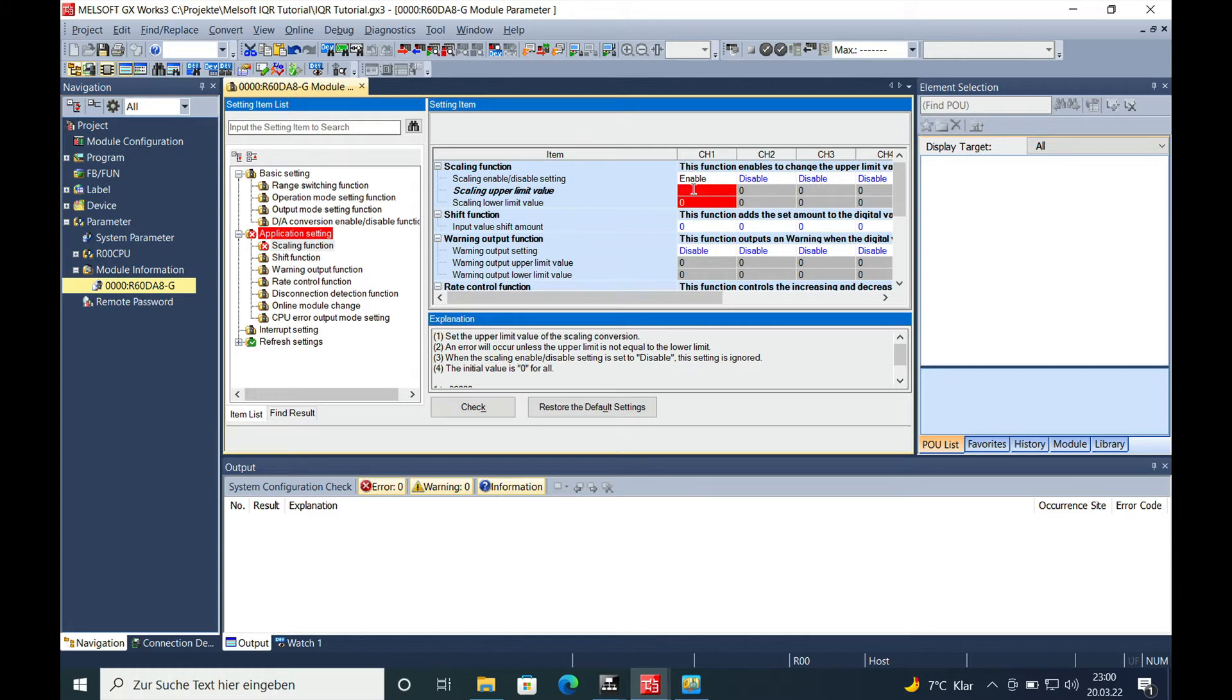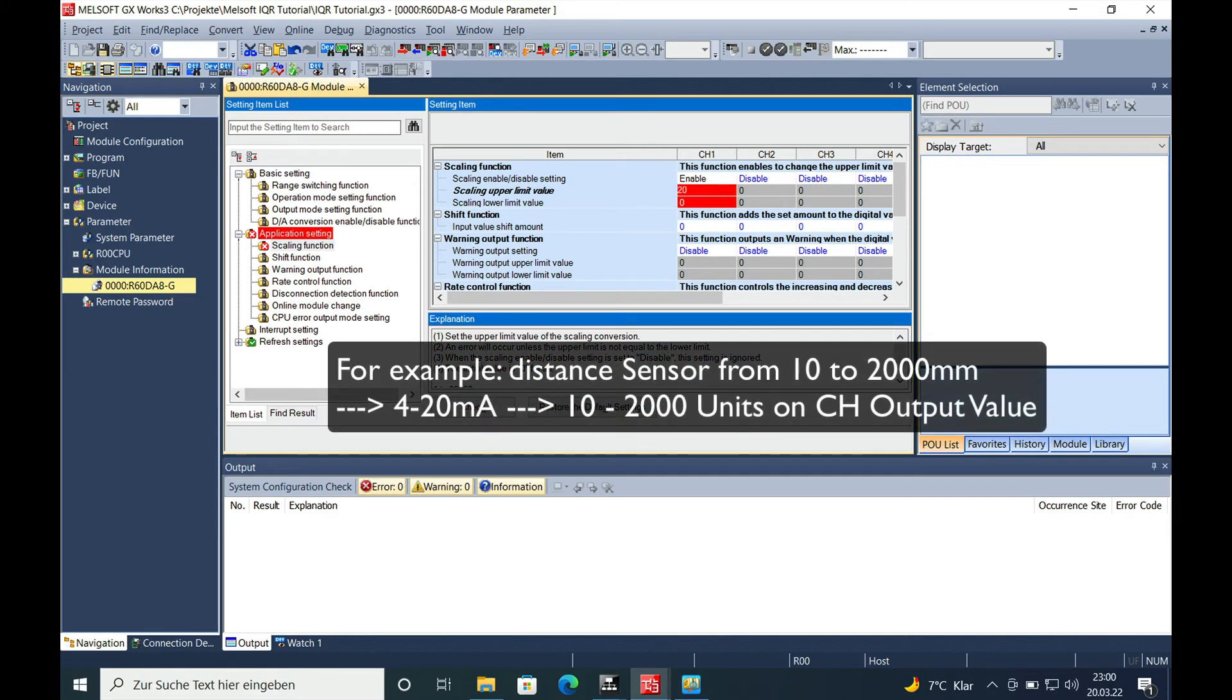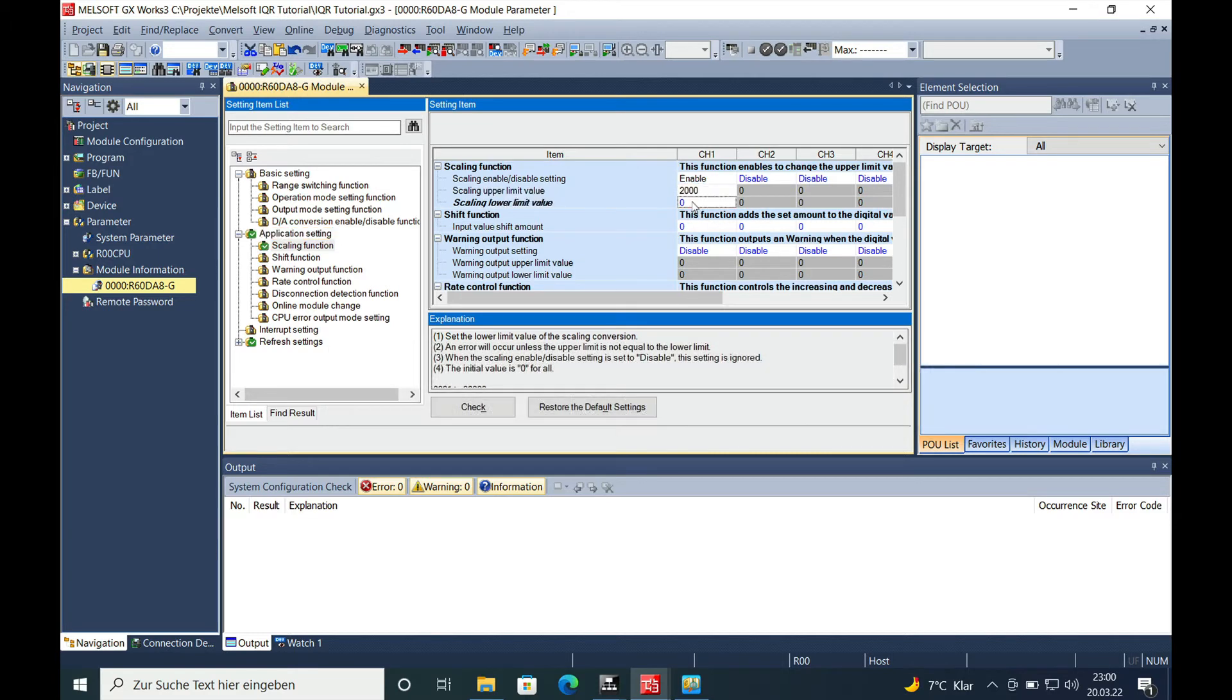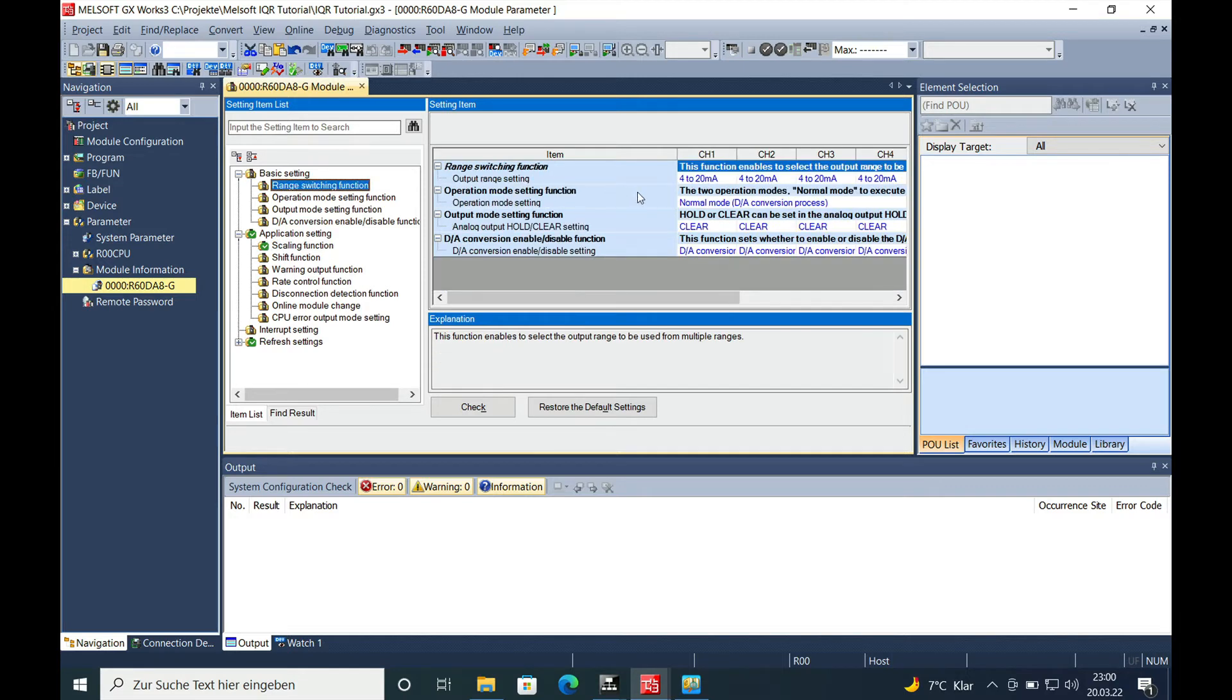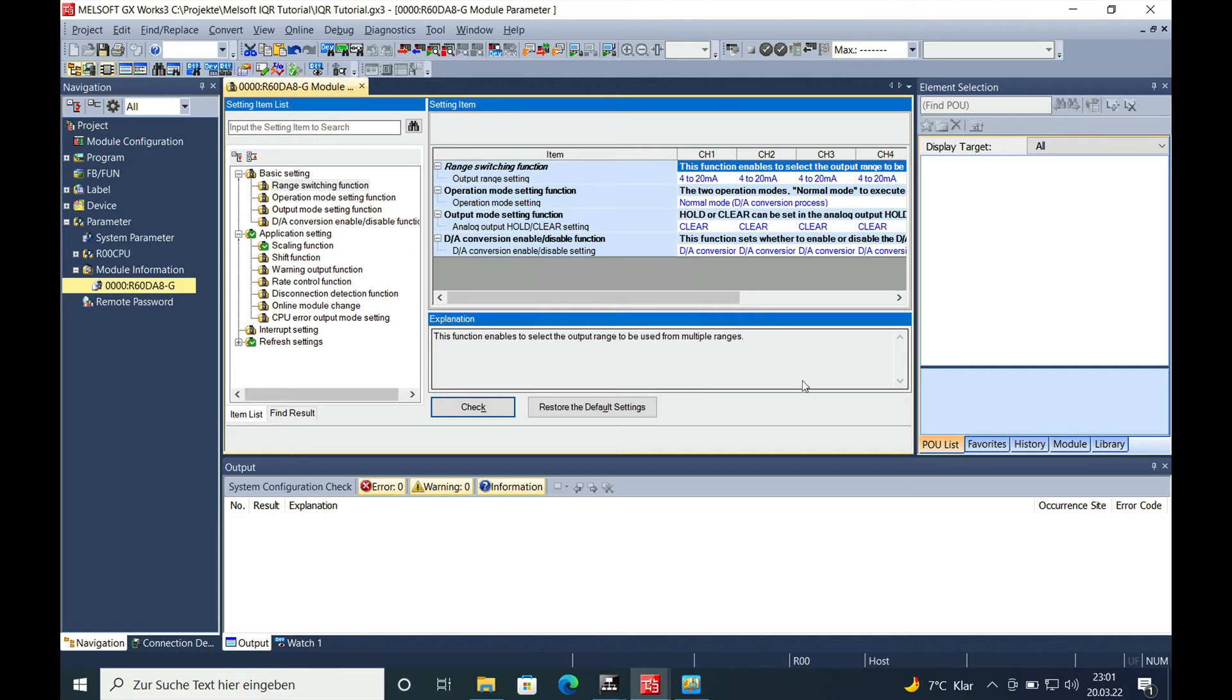Put your maximum value in that you actually want to read from your sensor. Maybe it's just 2,000 mm for 10V or for 20mA maximum and minimum is 10 units. So you can say this is from 10 to 2,000 mm for example if you got a value from 4 to 20mA.